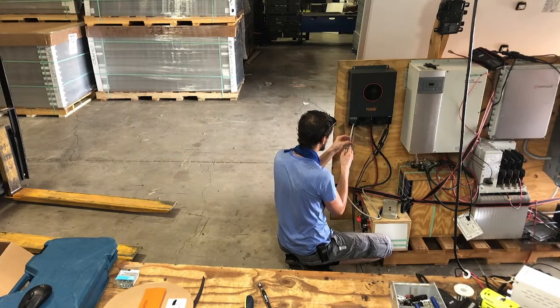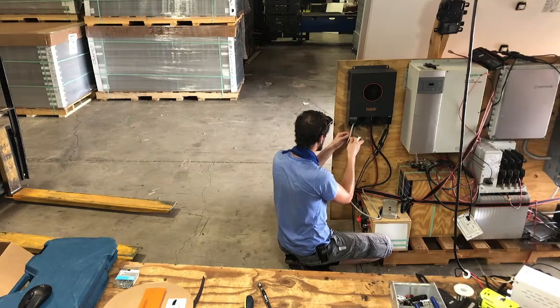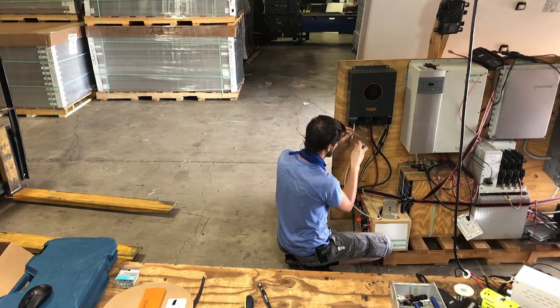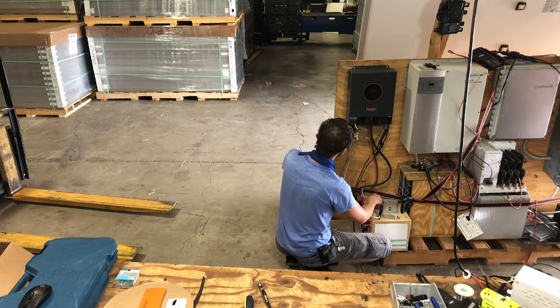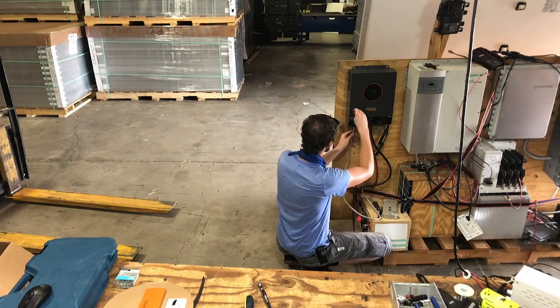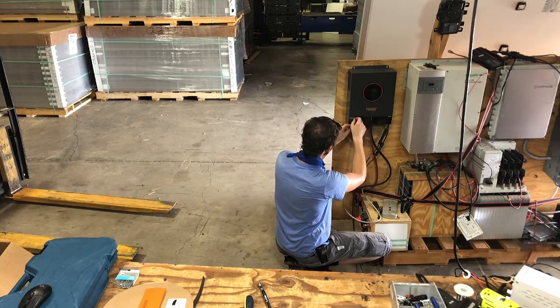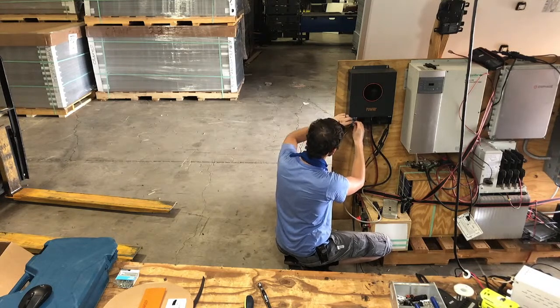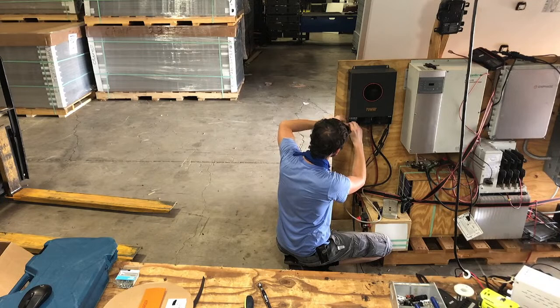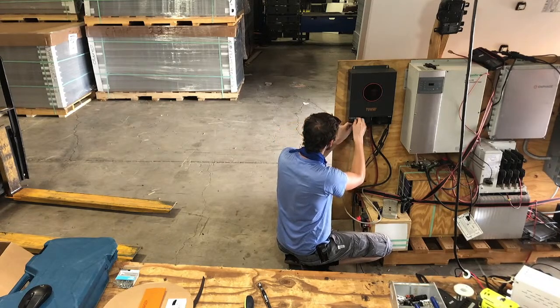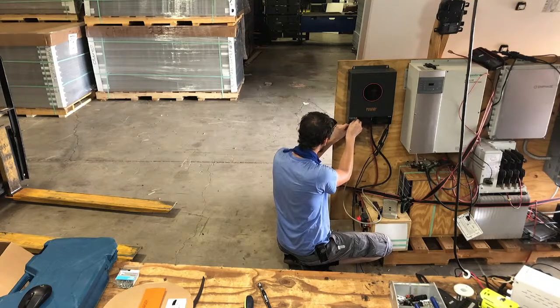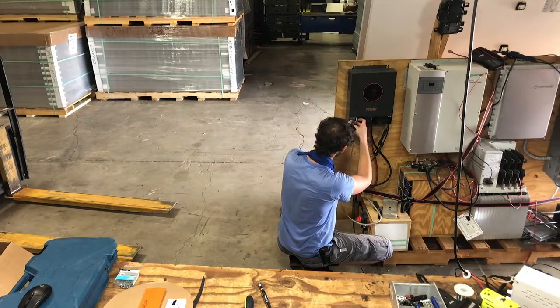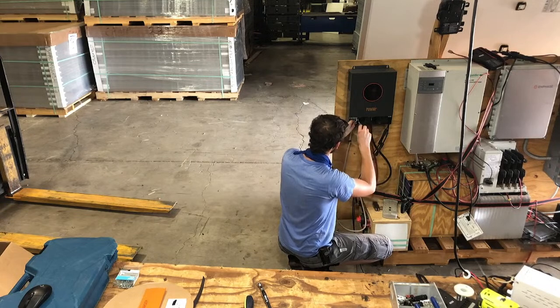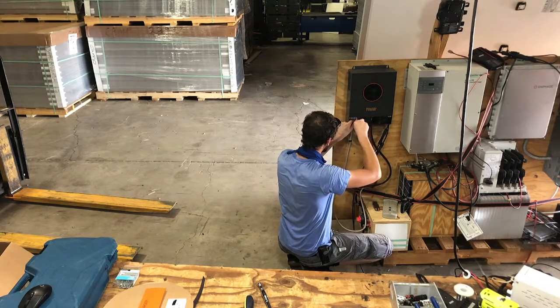Had somebody, and I thought I checked this when I built it out. I put a unit together for him, he hauled it up to Colorado to install it, and he's like, I shocked myself, as he was messing with neutral and ground. I said, well, that shouldn't shock you, those should be at the same potential, there should be no voltage between neutral and ground. Sure enough, as we tested it out, he said he thought he ohmed it out and everything, but apparently neutral and ground were not bonded in the inverter.